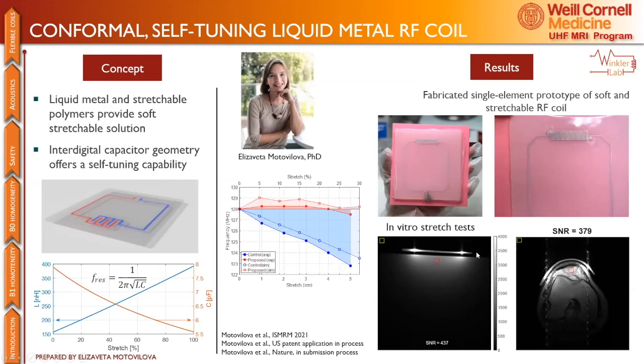Then we did in vitro stretch tests. We put the coil here on a phantom. You see the coil in this case because we didn't think about that, the coil needs to be doped with something to be invisible. But in this case, it's good because in the image, you see how it's stretched. So if you look at this, you see this coil being stretched, and the signal and SNR stay practically the same.